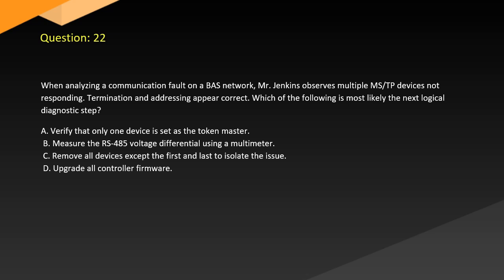Question 22. When analyzing a communication fault on a BAS network, Jenkins observes multiple MSTP devices not responding. Termination and addressing appear correct. Which of the following is most likely the next logical diagnostic step? A. Verify that only one device is set as the token master. B. Measure the RS-485 voltage differential using a multimeter. C. Remove all devices except the first and last to isolate the issue. D. Upgrade all controller firmware.